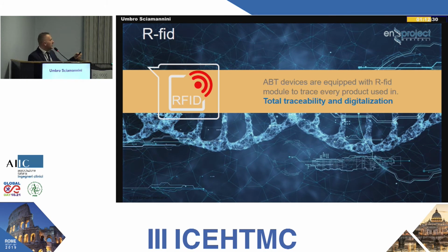RFID: the device has an RFID module to trace all chemical disinfectants used. When you refill the tank with disinfectant, you must first scan the RFID; if it's not recognized, it's impossible to refill the tank. This ensures only our product is used, guaranteeing complete disinfection.